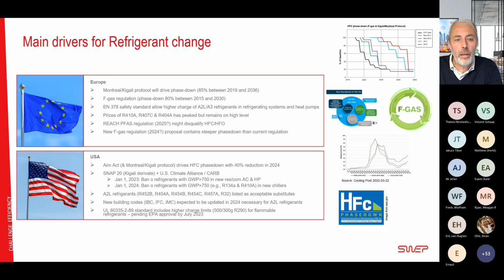We have also seen that several A2L refrigerants have been listed as acceptable substitutes in the United States. So presently, we have 6 candidates: R452B, R454A, R454B, R454C, R457A, and R32 are listed here. But the building codes also need to be in place to use these mildly flammable refrigerants. And the new building codes are expected to be updated in 2024, and those are necessary for the A2L refrigerants.